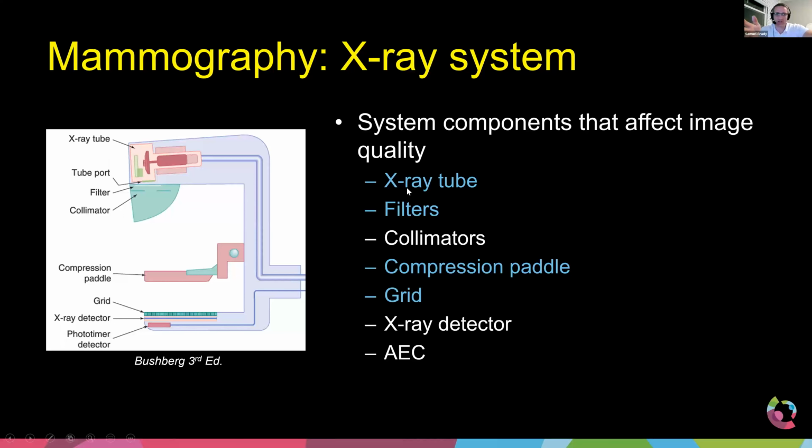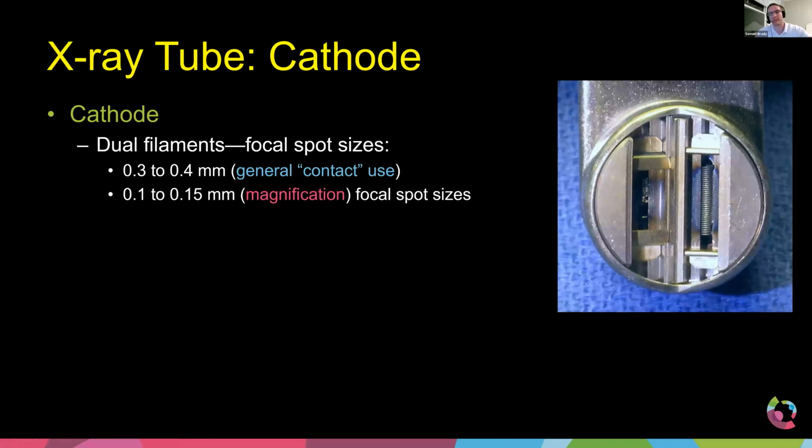So what I really want to do is talk about some of the more subtle things. I know you guys have all got your AEC systems up. I mean, that's just a standard process. Every mammogram has an AEC. Now, you may use a fixed technique, so therefore you have your charts. However you approach it, you've set up the right mA and kV combinations. That I'm using as my basic assumption for this talk. What I think will be interesting is when you look at all of these options to optimize, the compression paddle, I think, is the one that gives us the biggest variability to image quality. So we'll talk a bit about that one.